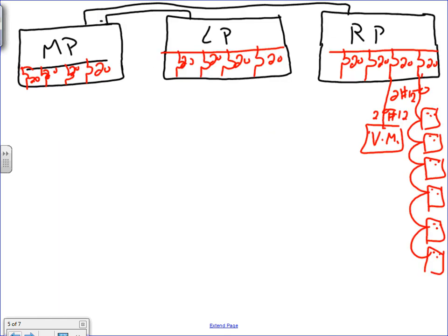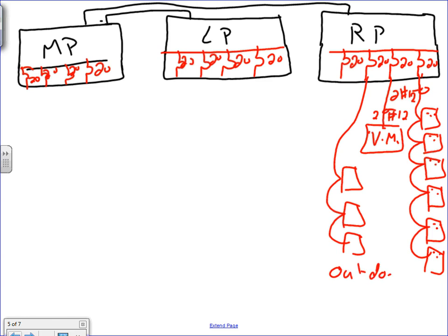And I'm going to add here these receptacles. I have 3 of them, and I put them in one circuit. This is outdoor. Can I drop these outdoor with these receptacles? Yes. Is it a good idea? No. This is another 2 conductors number 12. Now, when you go outdoor, I will warn you, depending how far you go, you might have to go up to number 10 for voltage drop. But we're assuming outdoor meaning just feeding the Christmas and holiday lights right next to the exit doors and so forth.